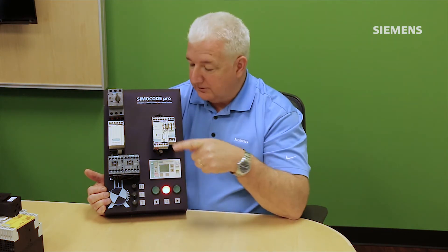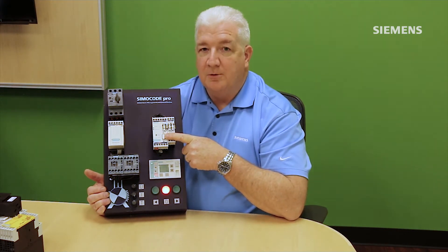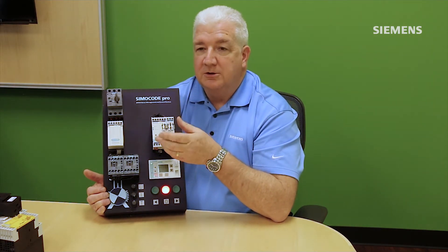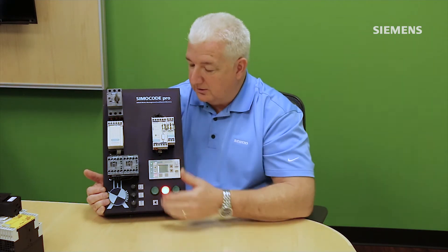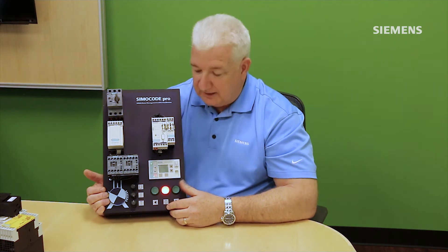The same principle applies to SIMOCODE. A start command can come from a local push button wired directly to the box, or from a command down the network cable. SIMOCODE then decides — based on whether it's in local or remote mode and whether all run permissives are satisfied — to send the output to the contactor to actually run the motor.